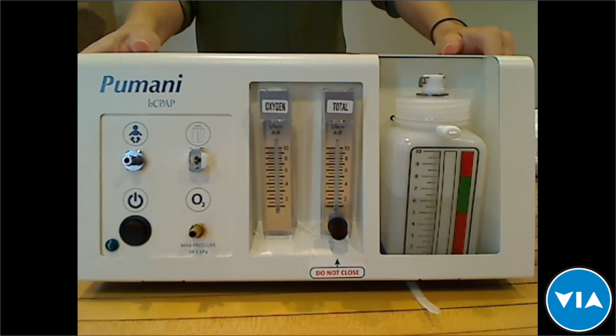So you have a water bottle here, and the height of water actually determines the air pressure that's delivered to the baby. So many people think that this is a humidifier. It's actually not a humidifier. It's the component that provides the pressure. And this is standard for any bubble CPAP device. And once I set up the machine, you'll see that when the machine is running and the baby is receiving the pressurized air, the water in this bottle will bubble, hence the name bubble CPAP.